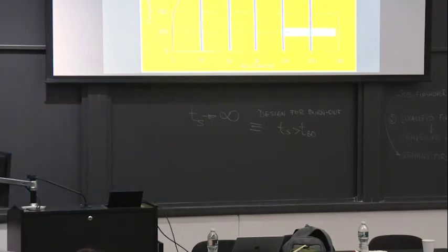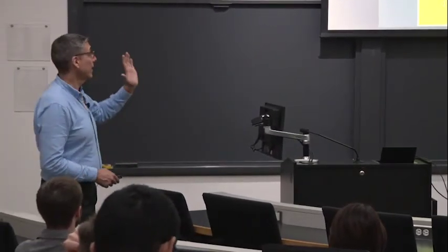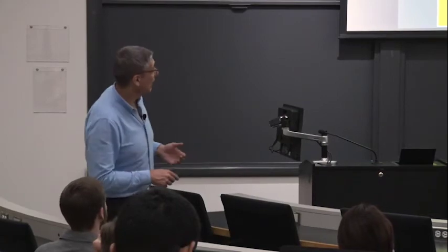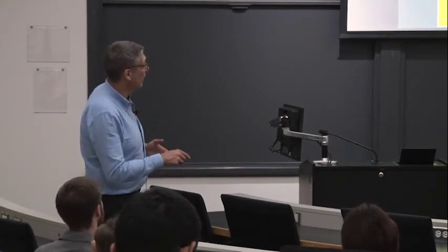Now, clearly, through the years, we have identified that certain fires are more onerous than that, like certain plastic fires, and so forth. So we have identified that actually that curve is not the worst possible fire. But the concept in itself is so over-dimensioned that nobody has been willing to change it, because everybody is comfortable that it is way beyond what we need, or at least we pretend that that's the case. Okay? But effectively, that's what it is. So as you increase the fuel load, you have a higher requirement.